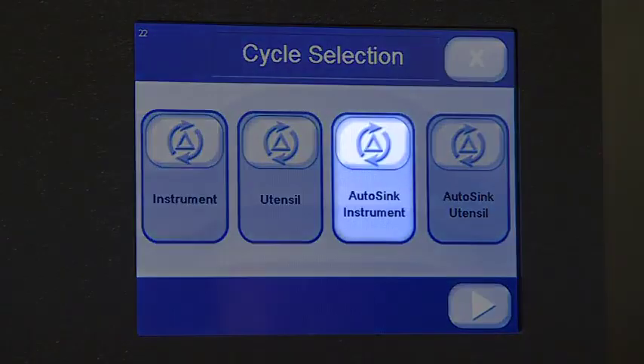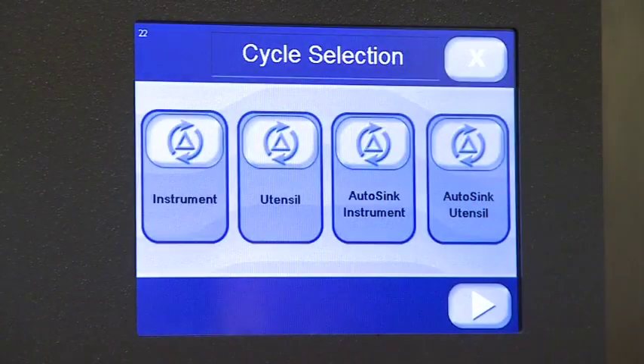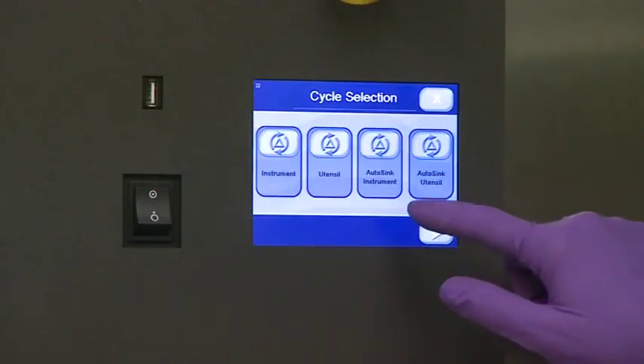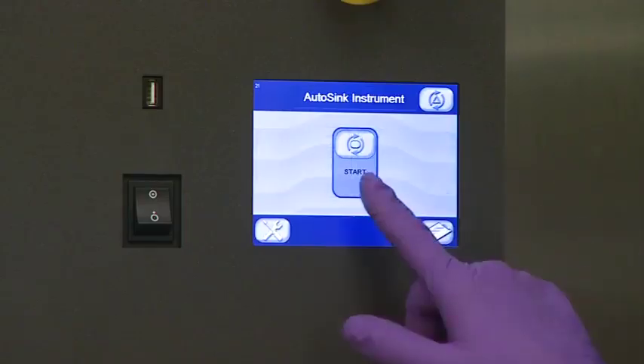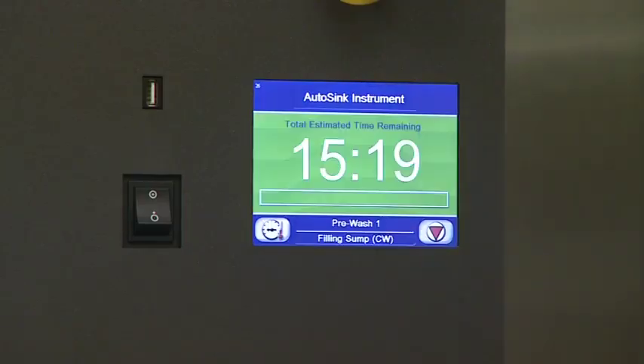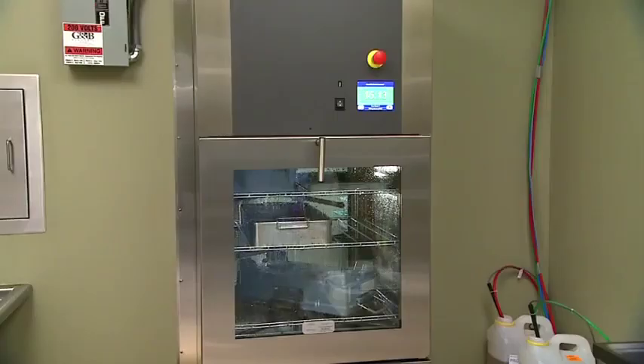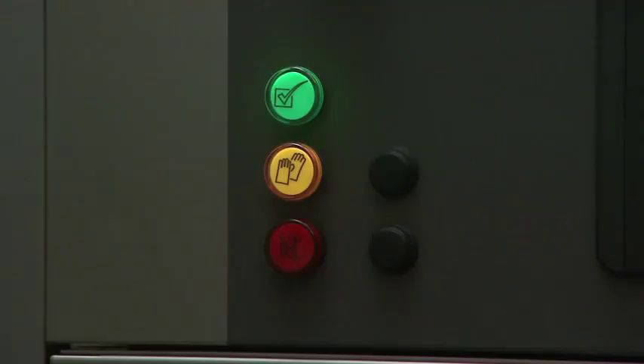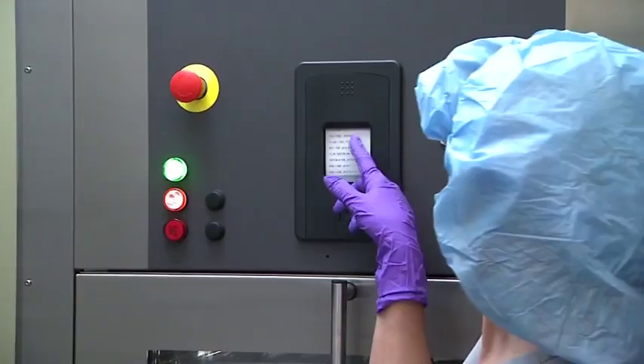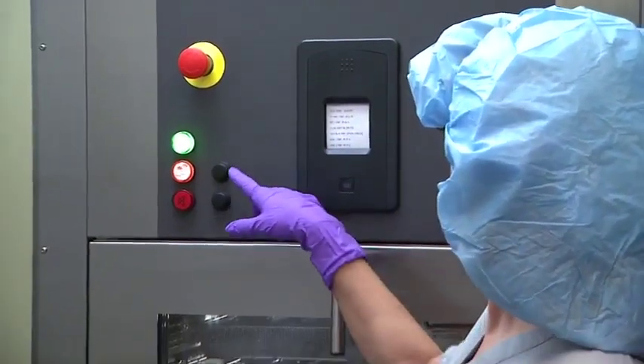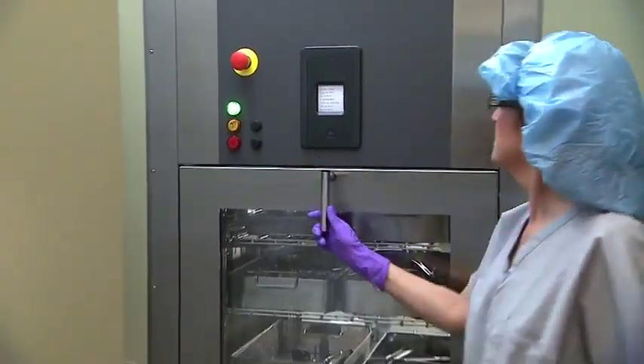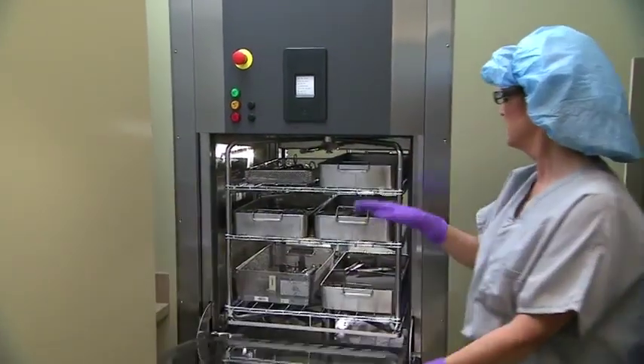Next, let's cover the AutoSink cycle. AutoSink can be selected from the cycle screen for quick turnaround items. Once selected, press Start. The cycle countdown screen appears and the AutoSink cycle runs. When complete, the controls confirmation screen will state that cleaning has been completed and disinfection was not included, and the yellow indicator light will illuminate. The operator must take the appropriate safety precautions and press the Acknowledge button that they are wearing appropriate personal protective equipment before they can open the unload door.